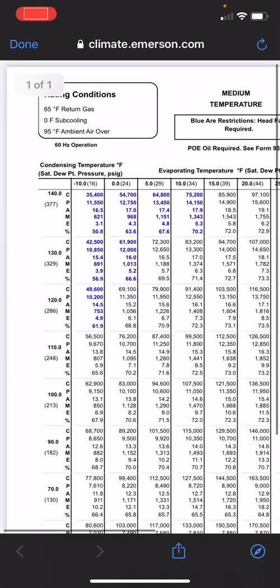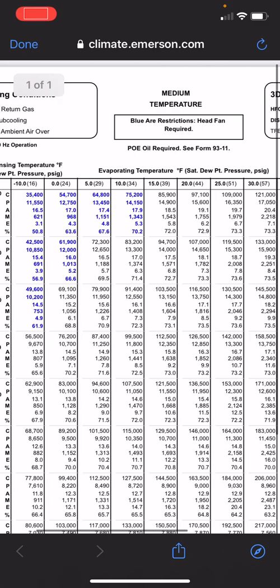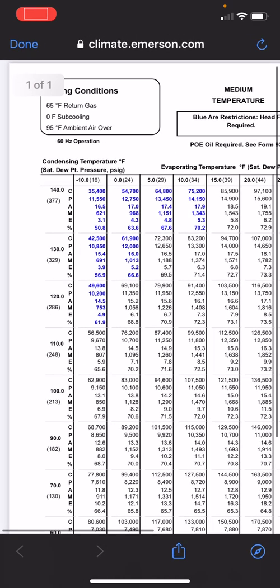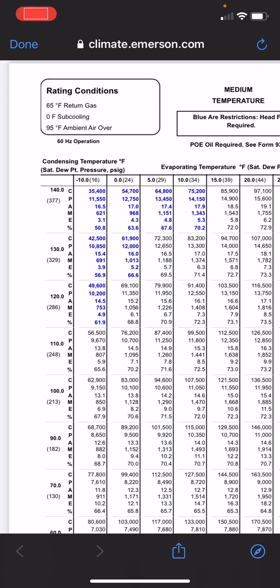So that means I need 1,000 CFM air blown over that compressor. The top is your evaporating temperature, the left side is your condensing temperature. So at 120, which is 286 PSI, and say 15 degrees Fahrenheit, 39 PSI, that compressor can do 103,000 BTUs and runs around 16.6 amps. And the mass flow is 1,600 pounds per hour. Really cool information.